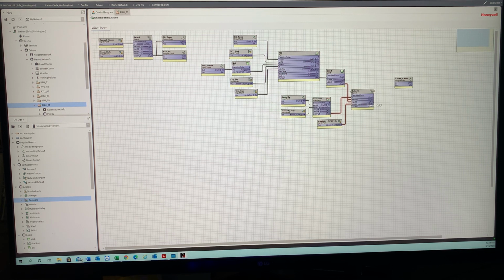Then we take our output and link it to our chill water valve. So now we have a real basic program for a chill water air handler. We can modify it depending on whether it's doing just space temperature control, where we're not doing a discharge air temp, versus doing the chill water valve based on space temp. It really just depends on the application and what the MEP is trying to design, and we modify it from there.